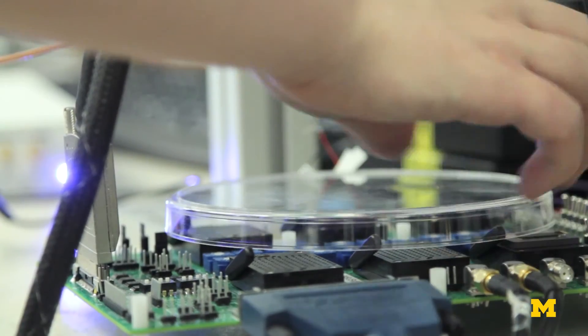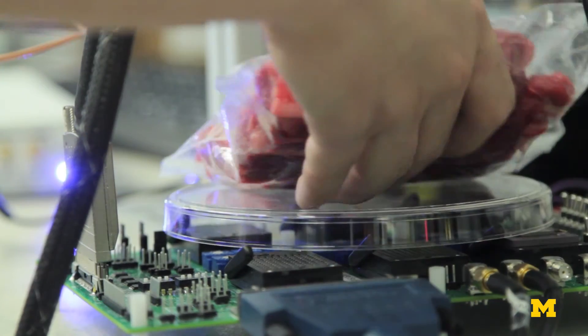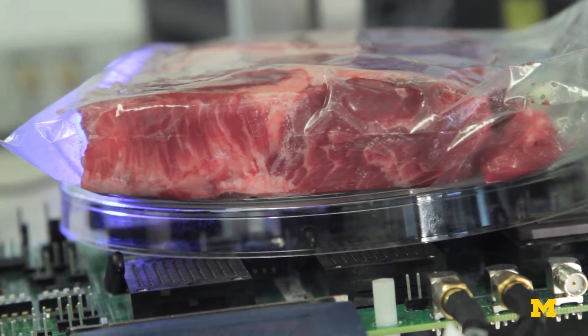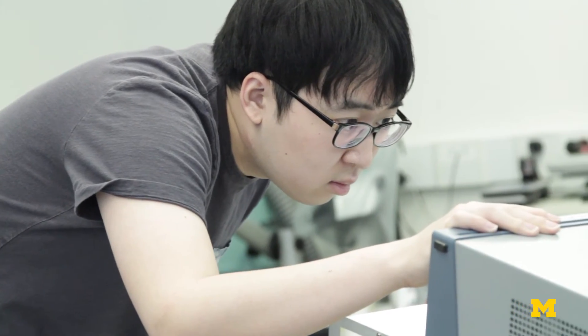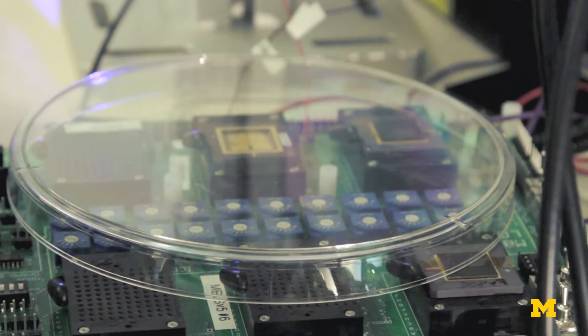The initial test — the initial bring-up and verification of the devices — is done on a benchtop. But at the same time we want to simulate what it's like to be inside the body and talking out. It communicates about a foot outside of the body, which is five to ten times longer than the next best reported number for communicating out of the body for something that small.